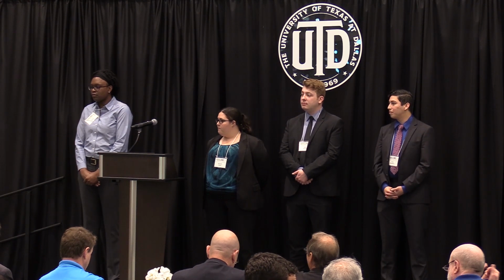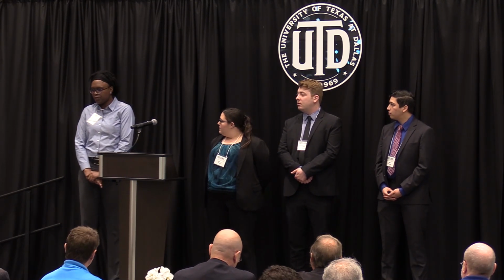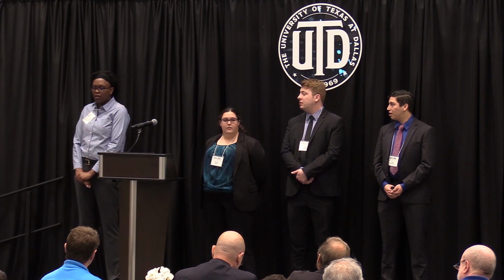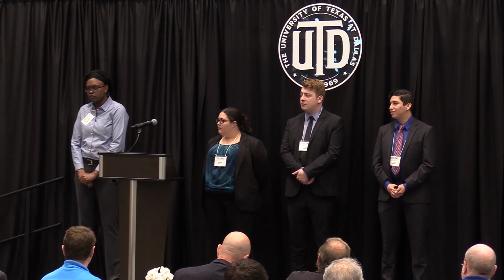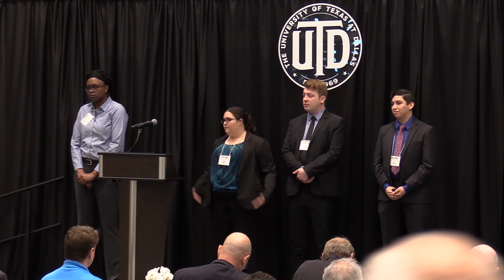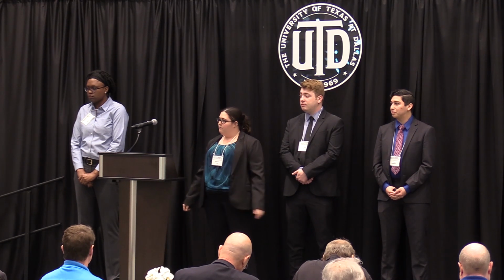Was your anechoic chamber certified? Did you know its characteristics? We did. Yes. We received it from ETS Lindgren. Let's see, the limits. Was it 30 to like 2 or 30 to 4? We believe it was 30 megahertz to 4 gigahertz rated. And since our signal was 30 megahertz, it was viable for our system level. So it should have shielded from both interference in those ranges as well as for any reflections that could happen.